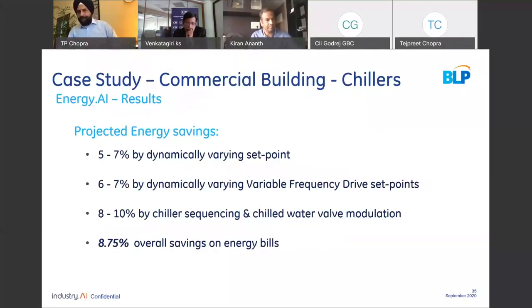So, just to quickly capture the three takeaways from this project: One, we got energy savings by dynamically changing the set points for these buildings or factories based on weather and environmental conditions and predicting what they need to be. Two, about 7% by dynamically varying the variable frequency drive set points. Three, close to about 10% by changing the chiller sequencing and the chilled water valve modulation. As a result, in just this limited period of time, we achieved 9% energy efficiency using these algorithms.